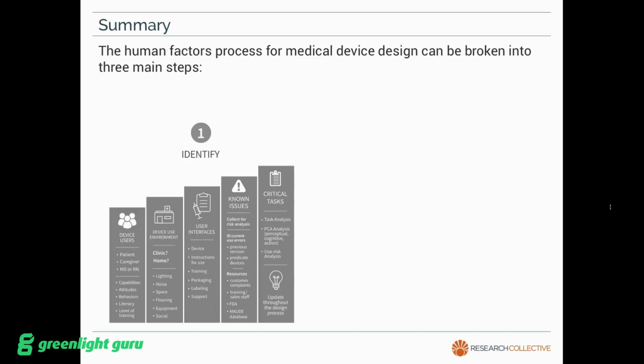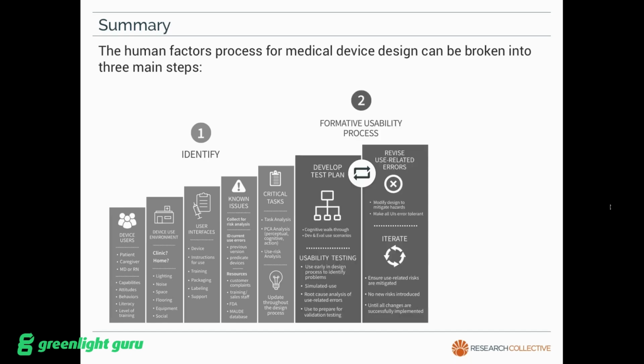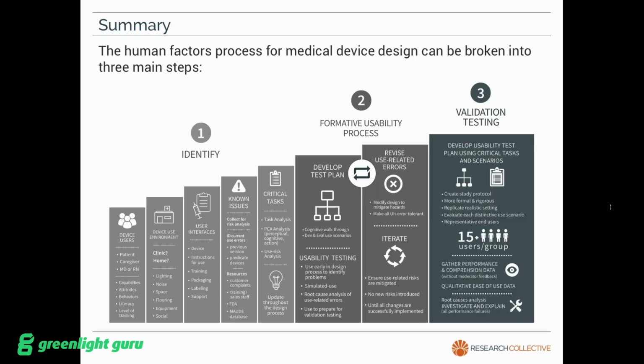And the human factors process for medical device design can be broken into 3 main steps. First, identify the users, the environments, interfaces, known issues, and critical tasks. Perform a formative usability process, or carry it out. So designing, evaluating, redesigning. This iterative approach will help flush out some of those design issues. And then lastly, validation testing, where our goal is to prove the device can be used safely and effectively by its users.